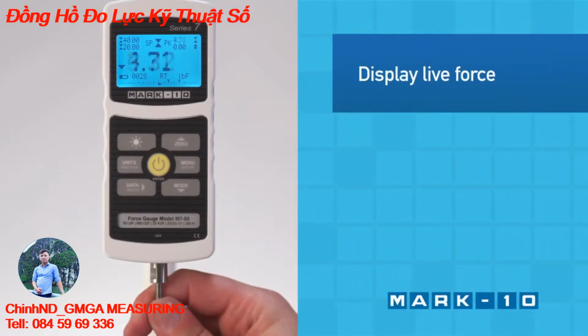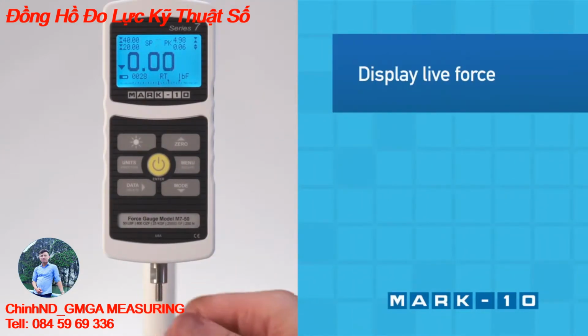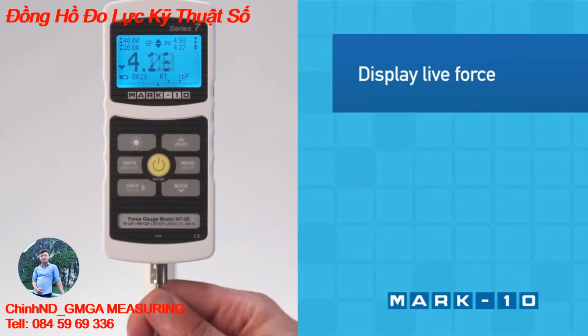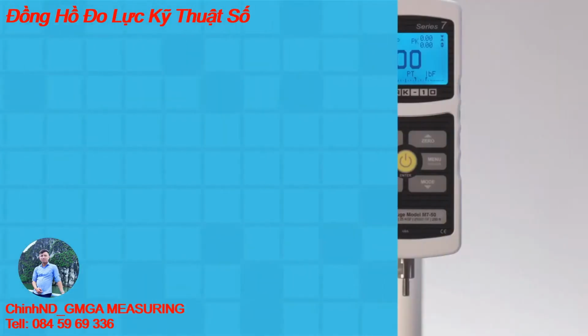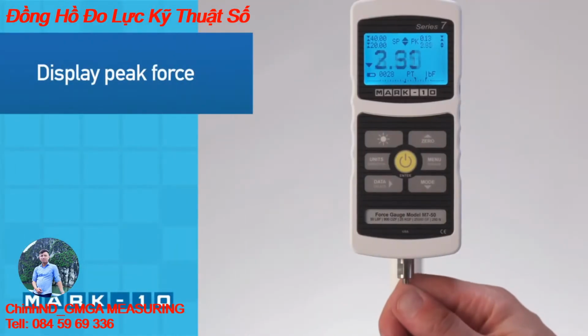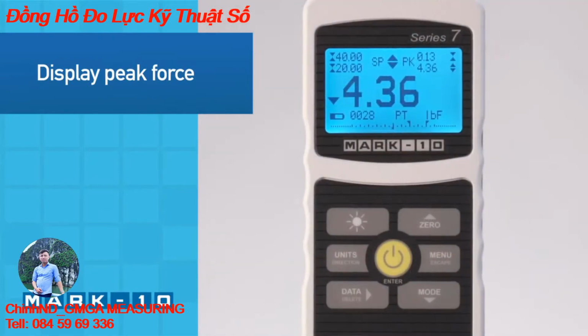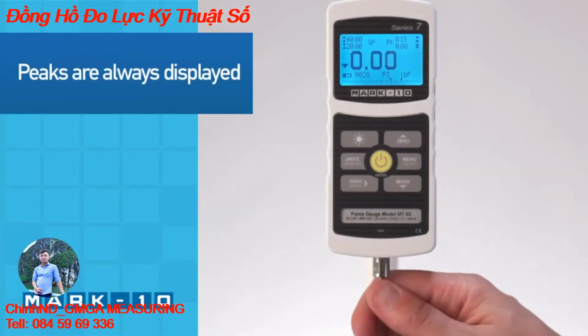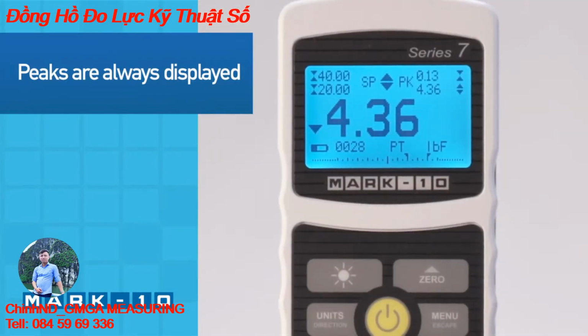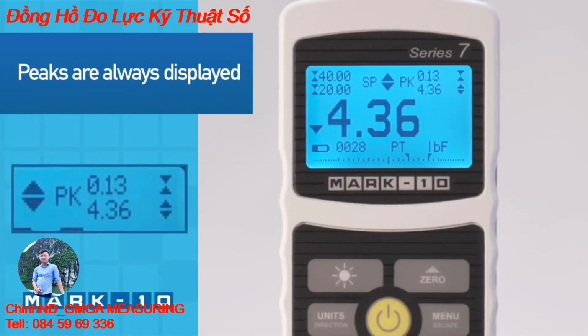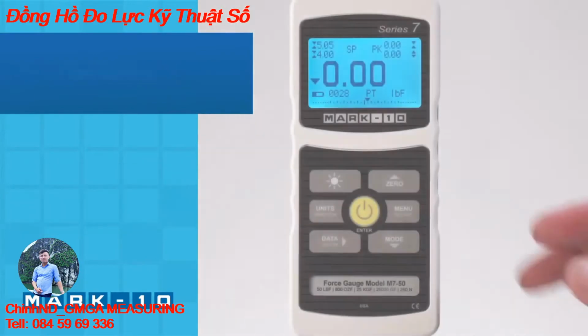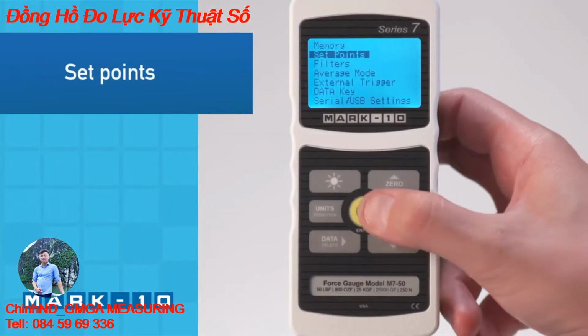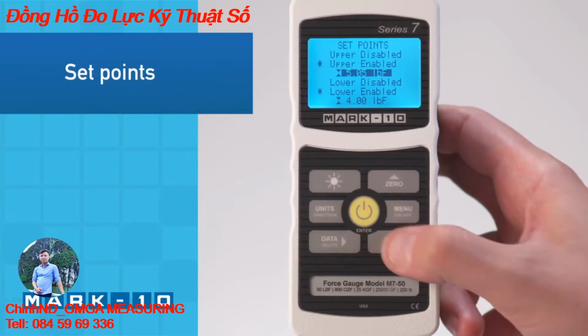Push and pull on the shaft to display the live compression or tension force in real-time mode. In peak mode, the display freezes when the peak force has been reached. Regardless of the mode, the tension and compression peaks are always shown in the upper right corner of the display. Upper and lower set points, shown in the upper left corner, may be configured for pass-fail testing.